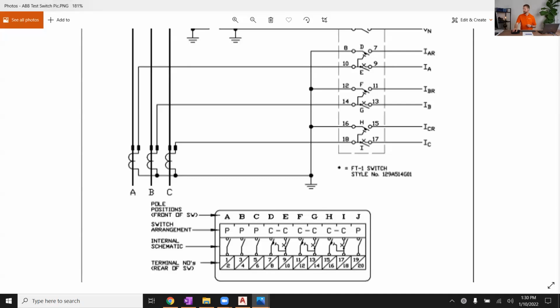Let me see if I can catch some of these other questions before we conclude today. Are there any conductor differences required for PT and CT circuits? Yes, I typically see larger conductors on the CT circuits because the amount of current flow you see in a PT secondary is fairly low. I think I told you, about 10 gauge is pretty common for a CT secondary circuit. I'd say 12 gauge is maybe somewhat common on a PT secondary circuit. Remember, with American wire gauge, it's the opposite direction. As the number goes up, the conductor is getting smaller.